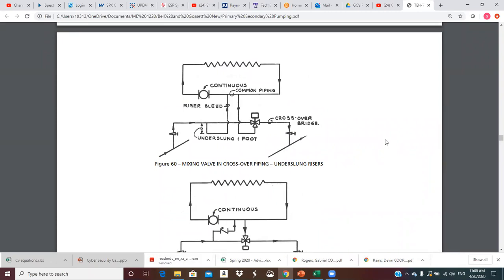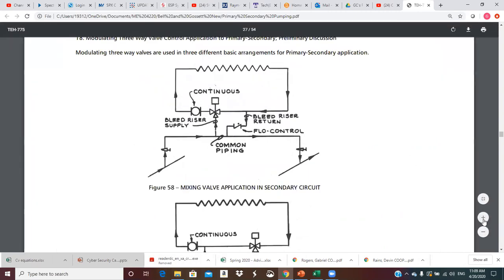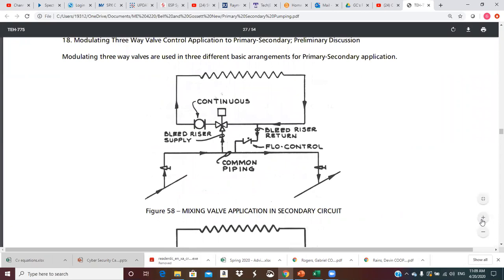The application in figure 58 has been in common usage for some time and despite some serious disadvantages has performed well, but we want to illustrate those disadvantages. Problem one: the three-way valve is interposed as a pressure drop directly at the secondary pump suction. Should valve pressure drop be high enough, the secondary pump can go into cavitation, resulting in pump damage and reduced flow rate. This valve, which often even when wide open has a significant pressure drop for controllability, is sitting right there on the suction — not a good situation.